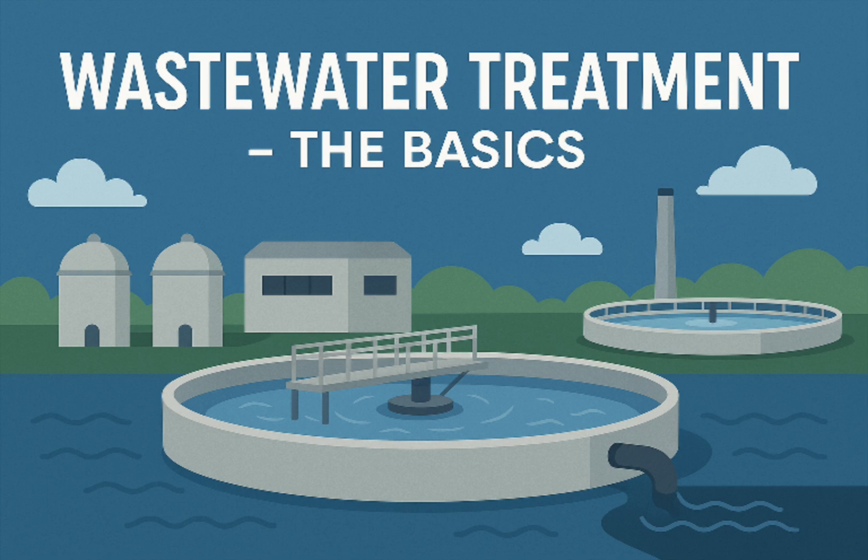How do those individual household systems work? Right, so septic systems serve homes not connected to a municipal sewer. All the wastewater flows into a buried septic tank. And inside the tank, same idea as primary settling? Pretty much. Solids settle to the bottom as sludge, grease and lighter stuff floats as scum. Anaerobic bacteria start breaking down some of the solids in the tank. Then the partially treated liquid, the effluent, flows out of the tank.